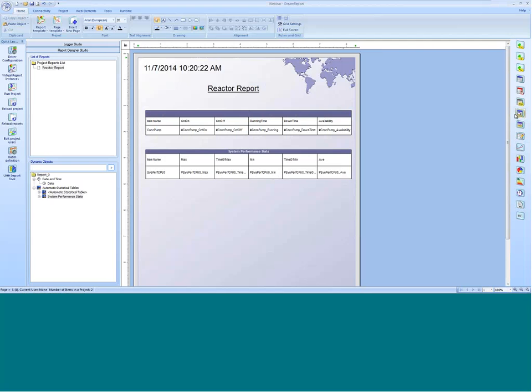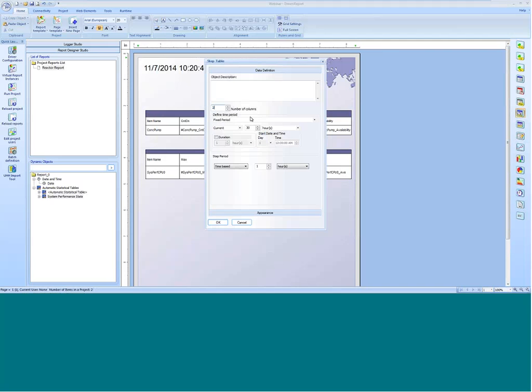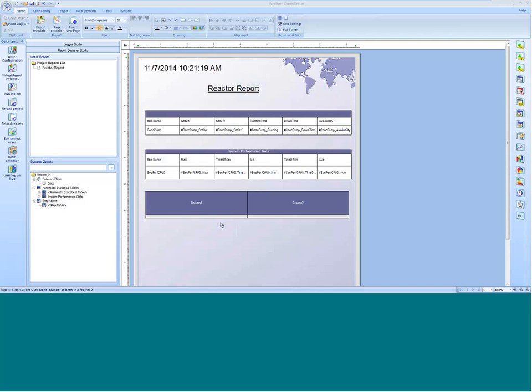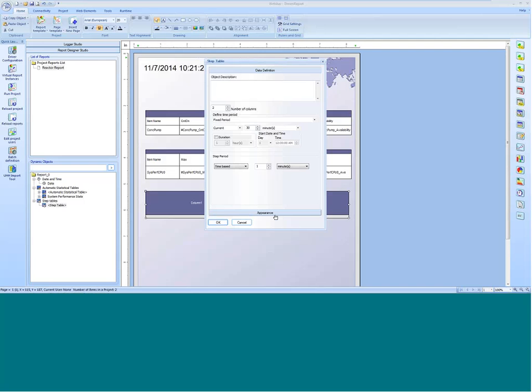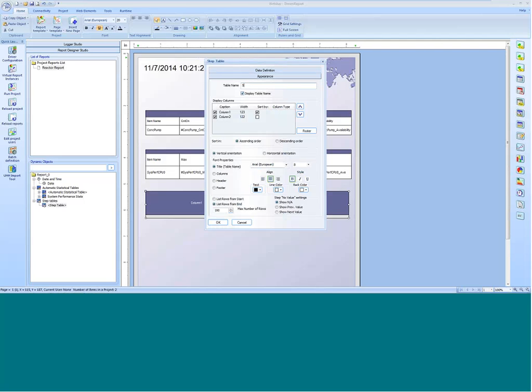Now I've got a new Automatic Statistical Table for System Performance. Let's create a Step Table next. Over on the right-hand side, I'll click Step Table and draw another object on my report. I'll have two columns in this Step Table. The Step Table allows us to — over the current 30 minutes — show us the value every minute. So if you had a daily report needing to report on 15-minute data, you could make the time period one day and the step period 15 minutes. If it's a weekly report with daily information, the fixed period could be one week and the step period one day. I'll click Appearance at the bottom and give my table the name Step Table, and give my first column the caption Time.